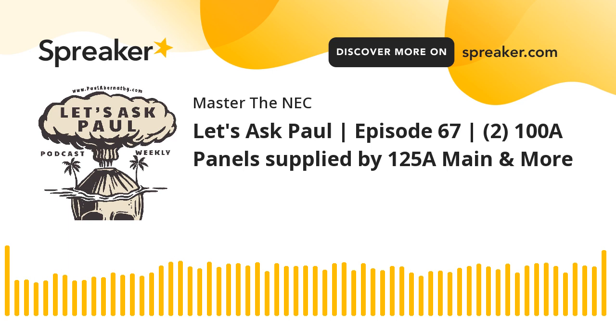So he feels very comfortable with this. So that means that the 2 70 amp breakers and the 1 60 amp breaker, they have feeders that are rated for 100 amperes, and they're terminating it in a 125 amp panel. That's perfectly fine. You can have a panel rating which exceeds the rating that you're using as the protection for that panel. That's fine. You're still protecting that panel at less than what the rating is of the enclosure. And it's very common to have a 100 amp panel that actually has a rating of 125. So again, you have to look at your panels, look at whatever the label says on it. But here, I have no problem. There's no problem at all with the 70 amp breaker with a feeder that's rated for 100 amperes feeding a 125 amp panel. That's no problem at all.